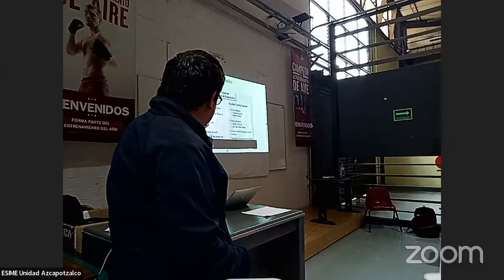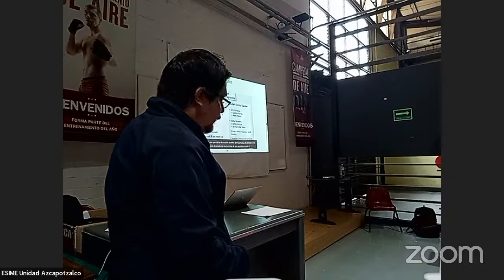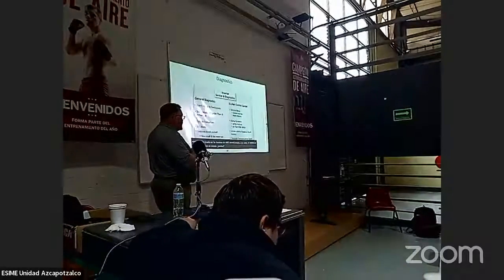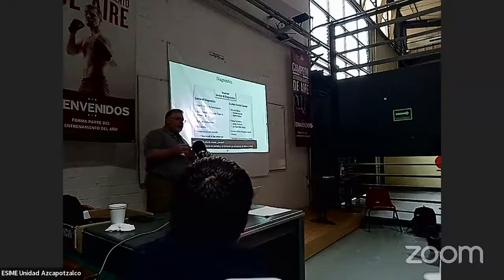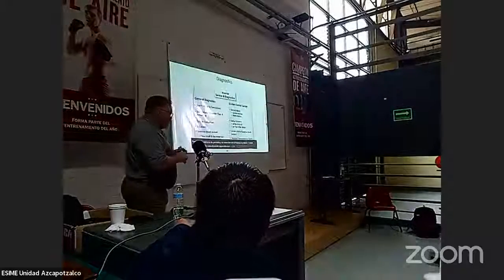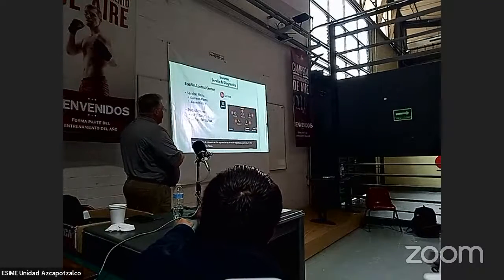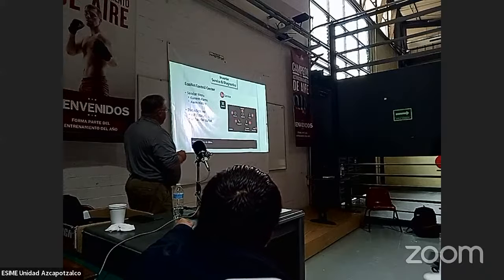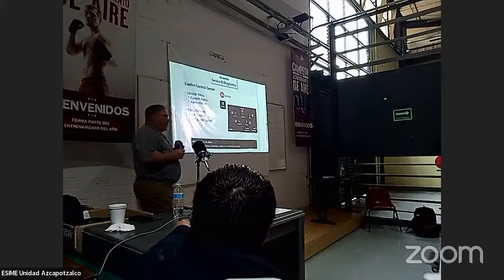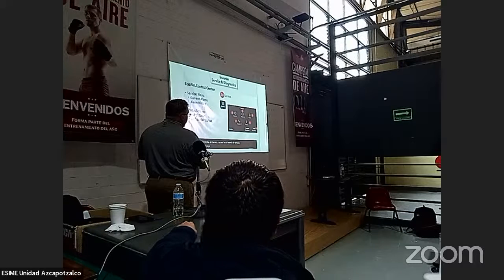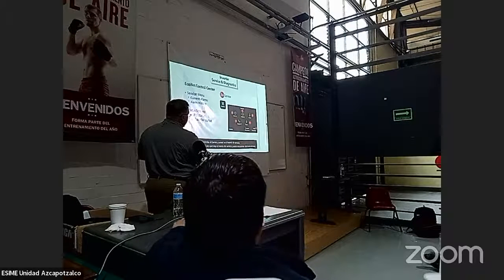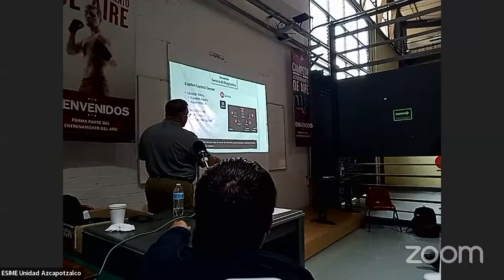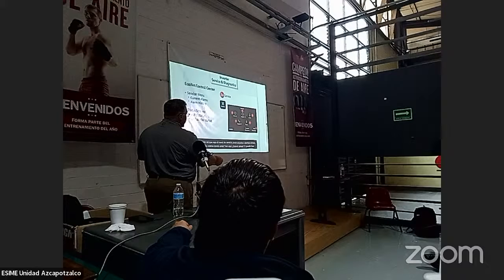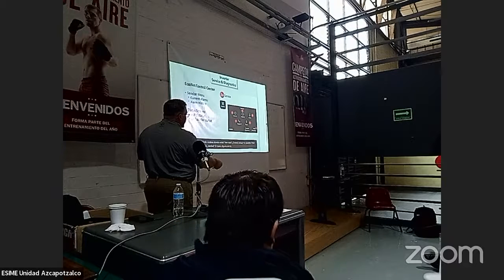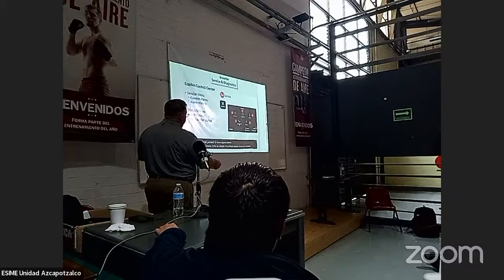If you pull up status screens on the EcoNet, you can look at your AC status, air handler status, right? You can take screenshots of the EcoNet with all history. We have separate communication faults in the registry, so you'll see different types of faults. So, EcoNet Control Center, you go to the service menu. Once you go to the service menu, you find current alarms. You can click on history, right? You have the alerts. You can do a furnace checkout, the outdoor unit checkout if you have a furnace, which you probably don't have here.